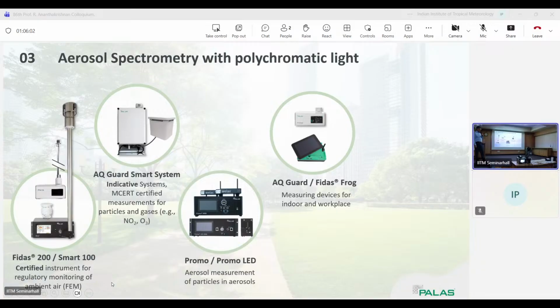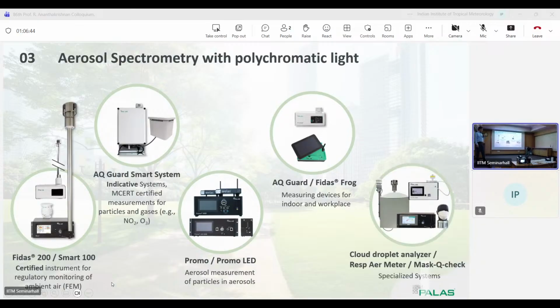In addition to that, we use spectrometry, of course, also in our industrial systems. Here you can see in front of you the PROMO system. That's one of the outcomes of the development. Sensors which are separated from the main unit, in this case 2 sensors, are predominantly used for filter efficiency measurement in filter media and filter elements, especially if it's about optical particles which can be measured optically. And in addition to that, also some specialties like the cloud droplet analyzer.